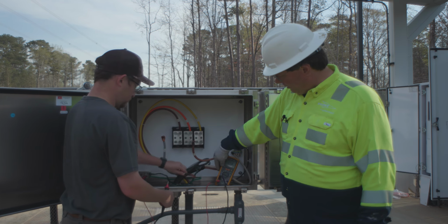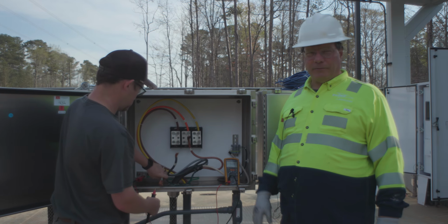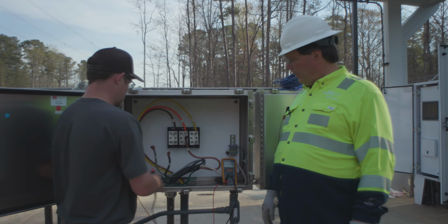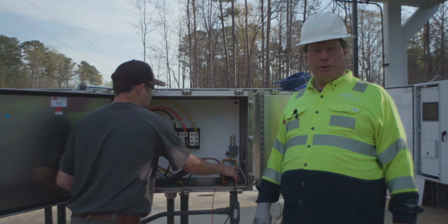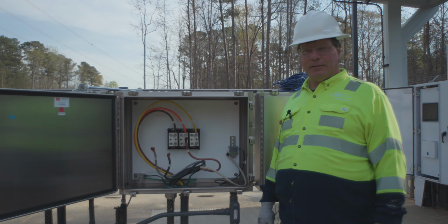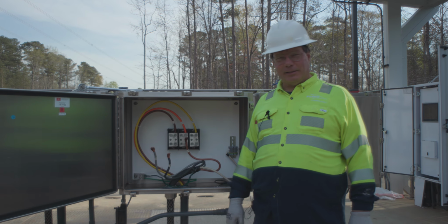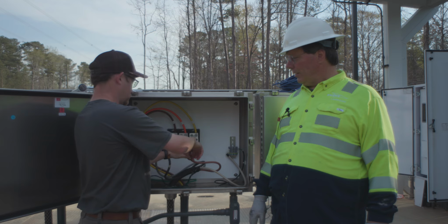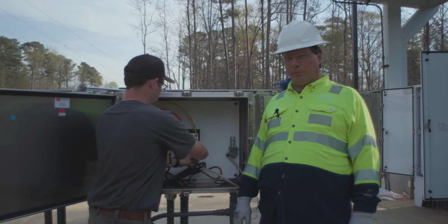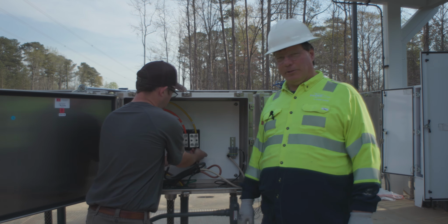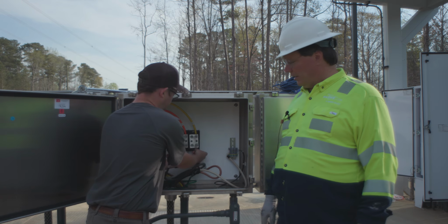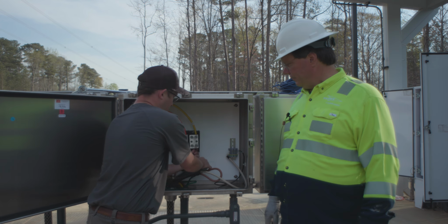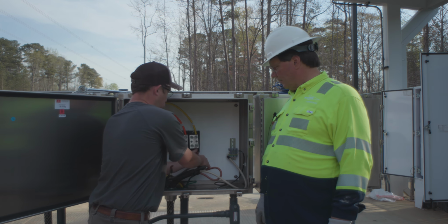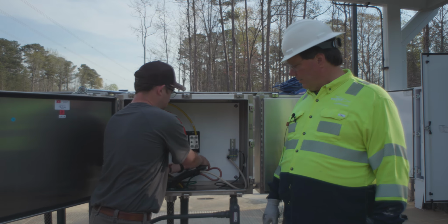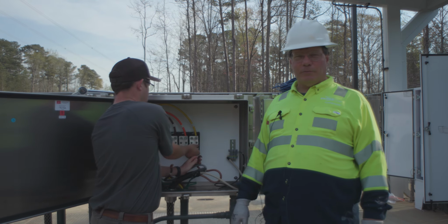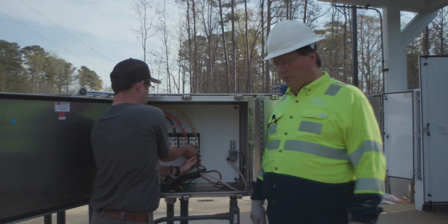The voltage we used was 525 volts DC, and that's a safety measure. We could do it at 1,000, but just in case we did not disconnect from a soft start or a VFD, using 525 volts prevents us from doing any serious damage to any components in the panel. And now we'll reconnect the leads, and then we'll check the sensor leads over here.